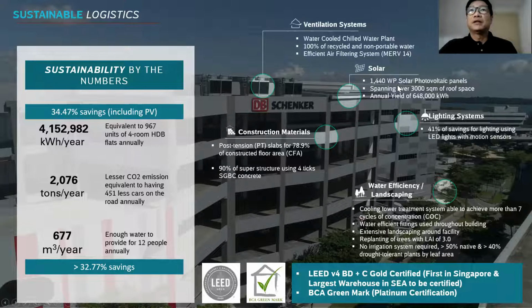In terms of ventilation systems, our system runs on a water-cooled chilled water plant system where 100% of recycled and non-potable water is reused. As such, we're able to save a substantial amount of water, and through efficient air filtering systems, MERV 14, the second highest. In terms of solar panels, we have a footprint of about 1,440 solar photovoltaic panels spanning across 3,000 square meters of roof space, with an annual yield of close to 650,000 kilowatt hours.